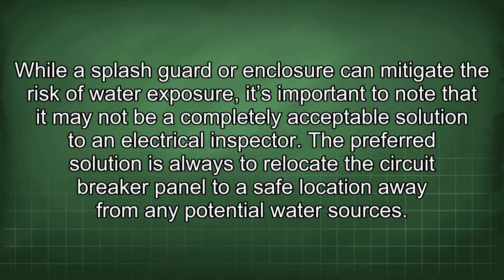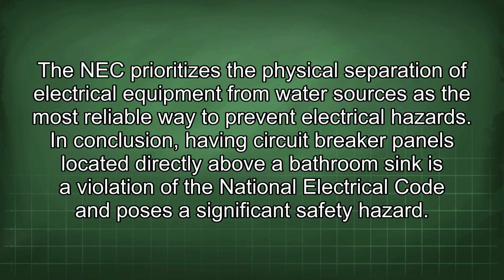While a splash guard or enclosure can mitigate the risk of water exposure, it's important to note that it may not be a completely acceptable solution to an electrical inspector. The preferred solution is always to relocate the circuit breaker panel to a safe location away from any potential water sources. The NEC prioritizes the physical separation of electrical equipment from water sources as the most reliable way to prevent electrical hazards. In conclusion, having circuit breaker panels located directly above a bathroom sink is a violation of the National Electrical Code and poses a significant safety hazard.